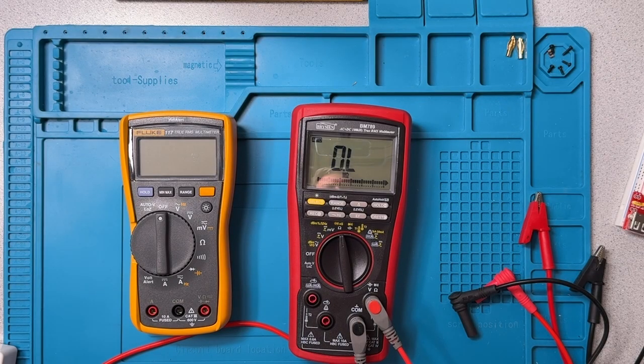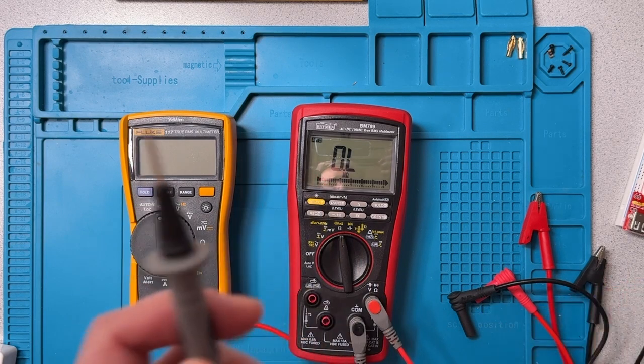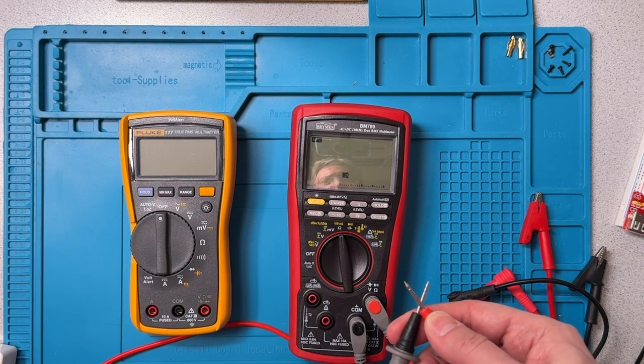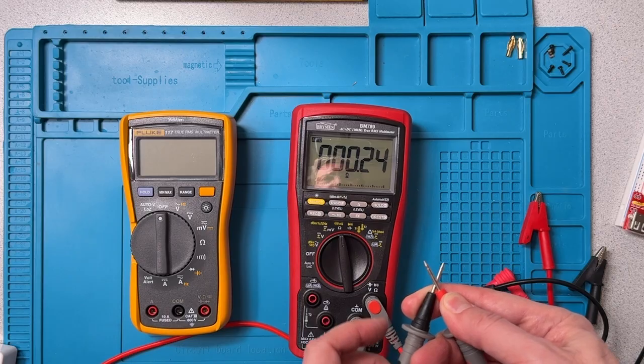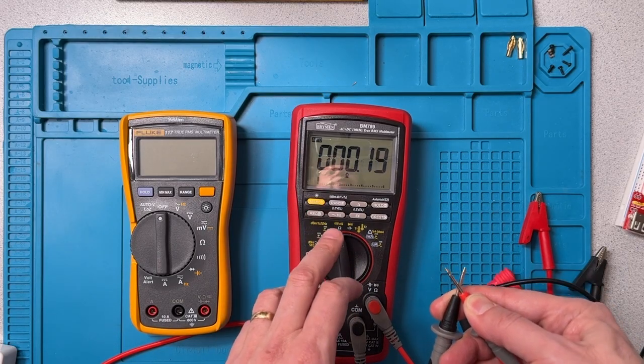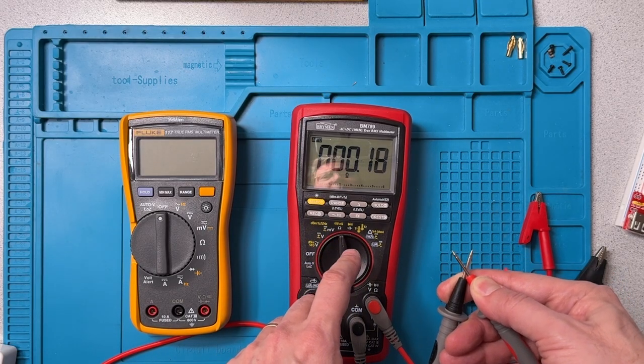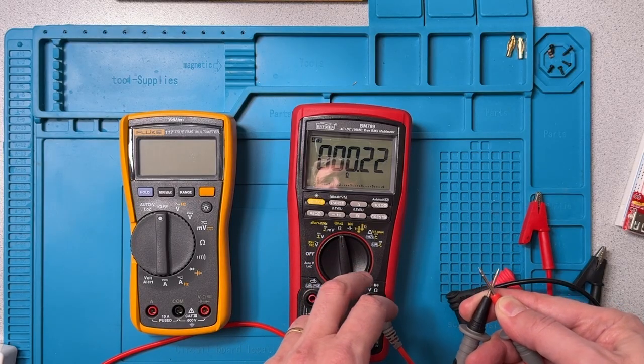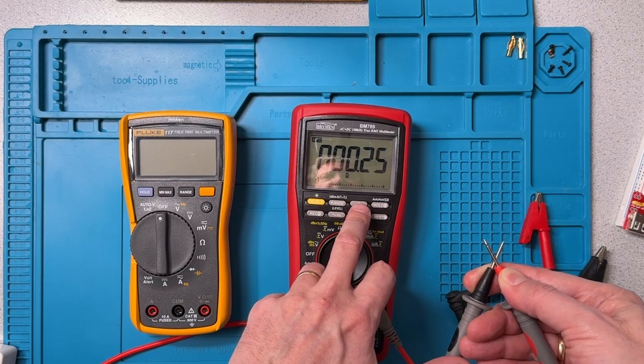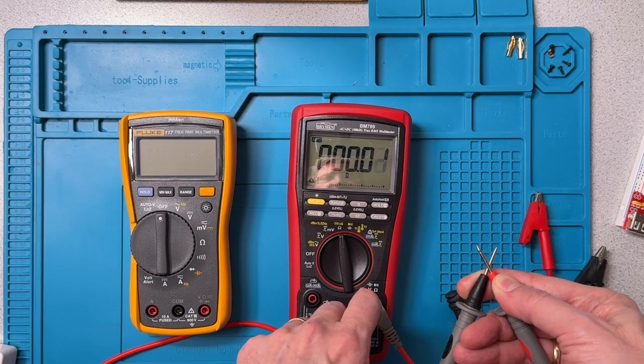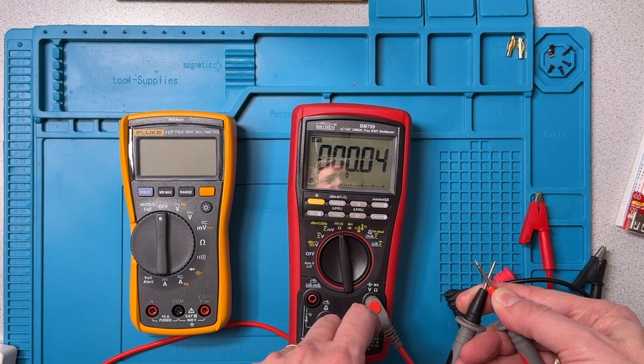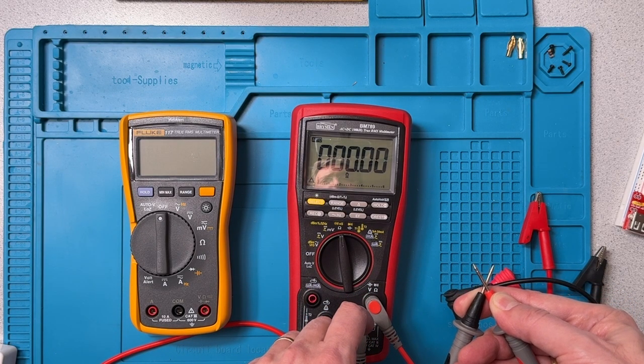Now the Brymen comes with a very nice set of silicone flexible probes, gold tipped, and the resistance of those probes doesn't even register. But if we use some other probes here, you can see that we've got about a 0.2 ohm resistance on the probes. And let's say we want to account for and zero that out, so we're not measuring the resistance of the probes. We can use this delta function. And that basically removes the resistance at that point, in a sense.